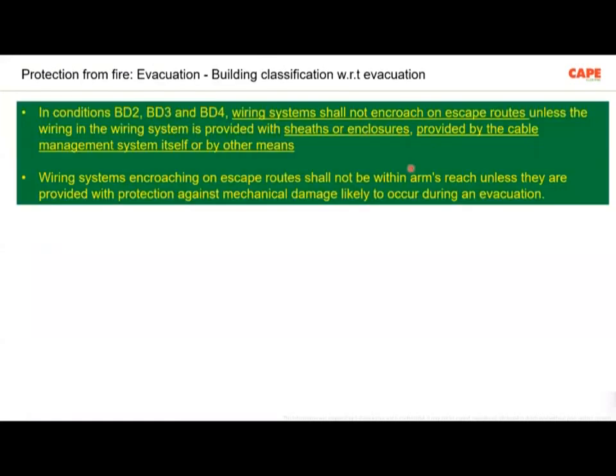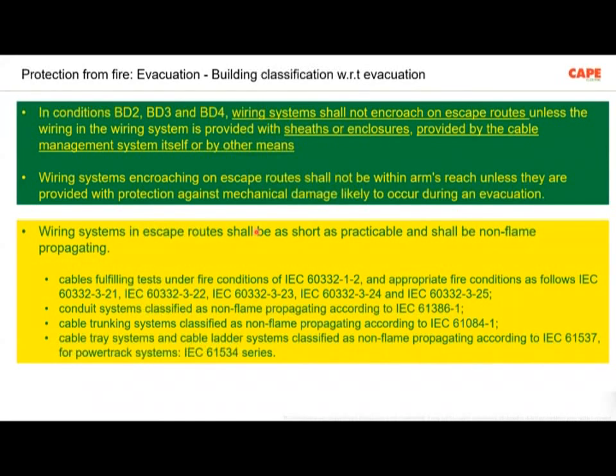Now, what do we require in this classification, BD2, BD3, and BD4? There are special requirements. You can go to clause number 4.2 of IS732, where these special requirements are very well documented. For example, in conditions BD2, BD3, BD4, wiring shall not encroach on escape routes unless the wiring system is provided with a sheath or enclosure, provided by the cable management system itself or by other means. Basically, what it says is you cannot hang your wires in the escape route. You have to fix them properly, and you have to have special protective measures. Number two, you cannot use normal light fittings. You need to have special light fittings. All these special additional requirements are included, and you can see this in IS732 clause number 4.3, sorry, it's not 4.2.